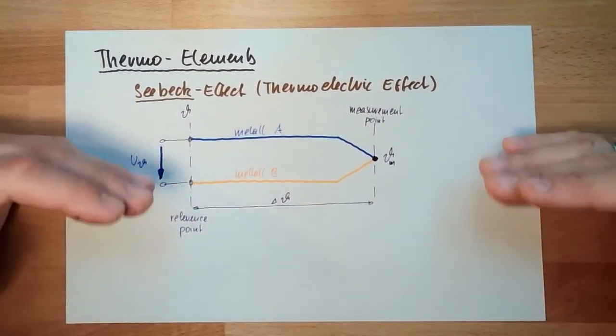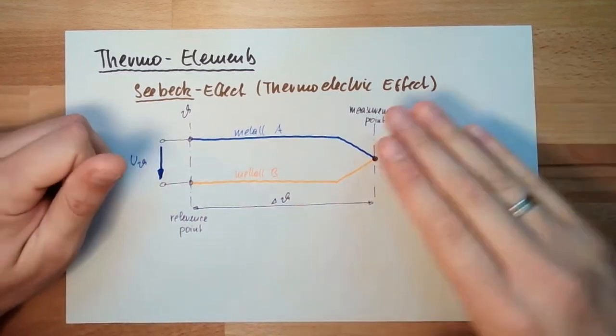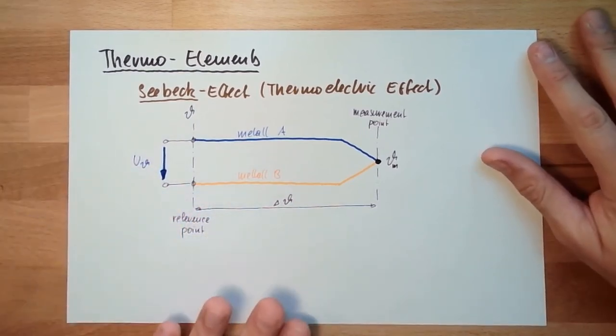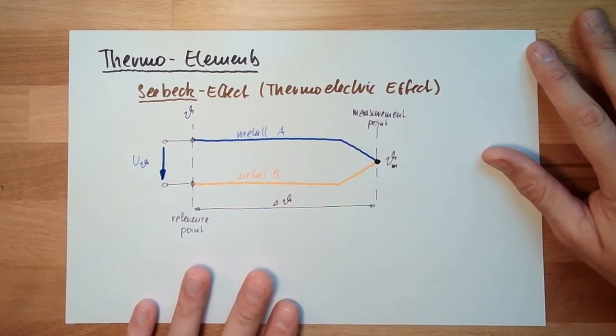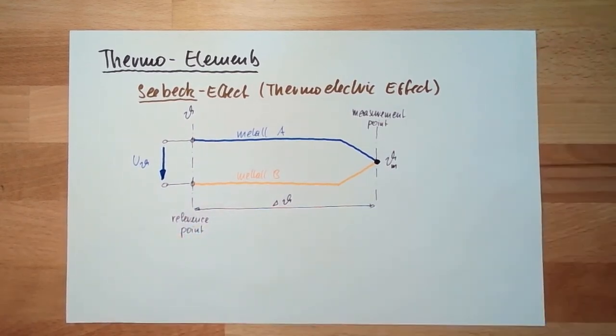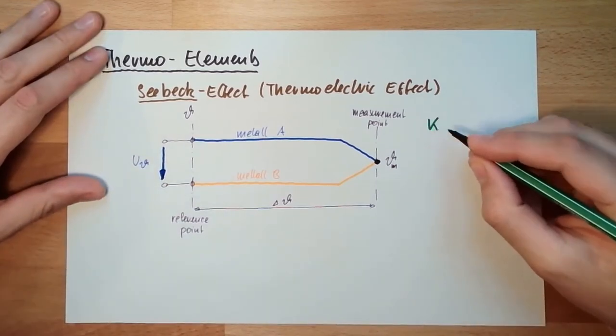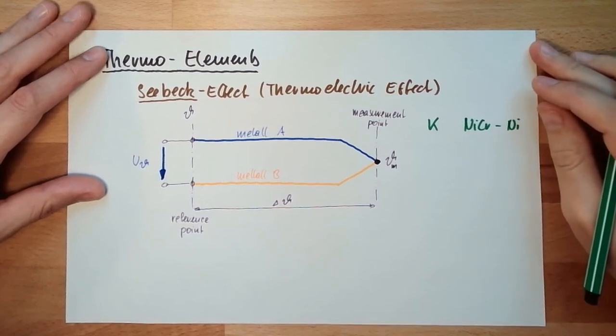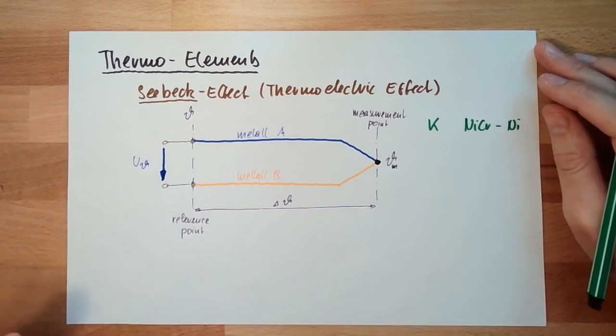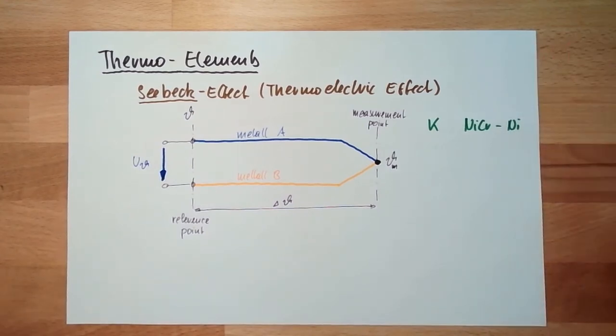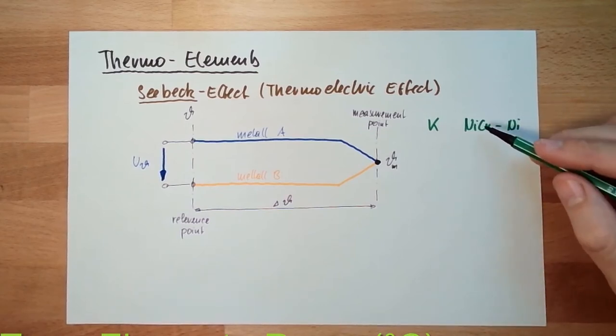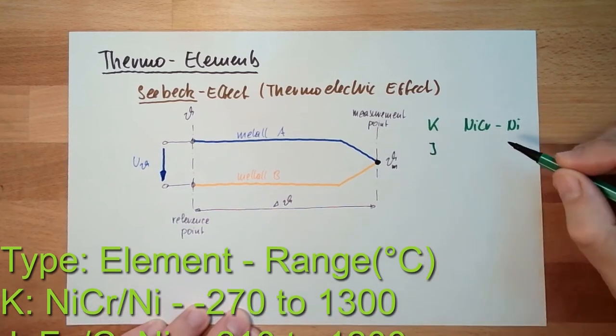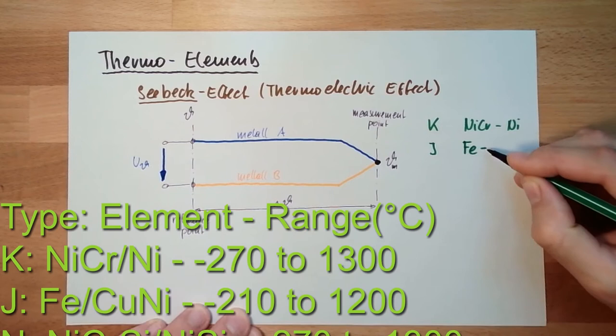In thermoelements, a lot of things are important. There are several types defined. The most commonly used type is type K - nickel-chrome-nickel. It's defined from minus 270 to up to 1300 degrees Celsius. Then there is type J - iron, copper-nickel.